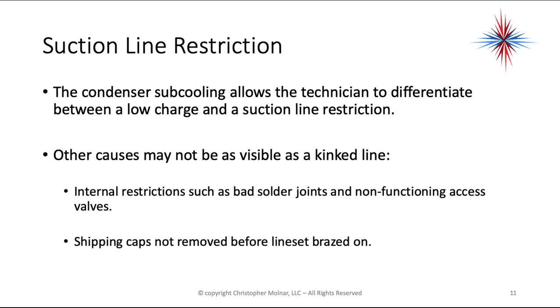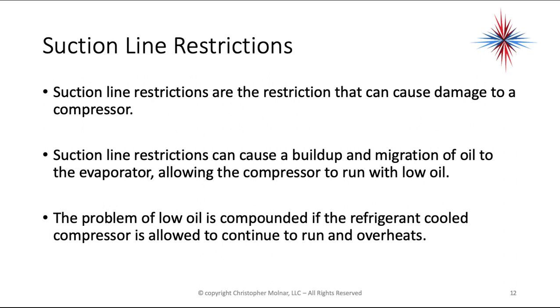The condenser sub-cooling allows the technician to differentiate between a low charge and a suction line restriction. Other causes may not be as visible as a kinked suction line — you can have internal restrictions such as bad solder joints and non-functioning access valves, or shipping caps that were not removed before the line set was brazed on. Suction line restrictions can cause damage to a compressor by causing a build-up and migration of oil to the evaporator, allowing the compressor to run with low oil levels. The problem of low oil is compounded in refrigerant-cooled compressors, as they will continue to run and overheat.